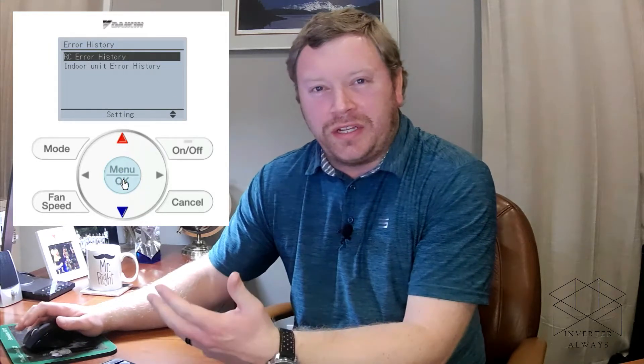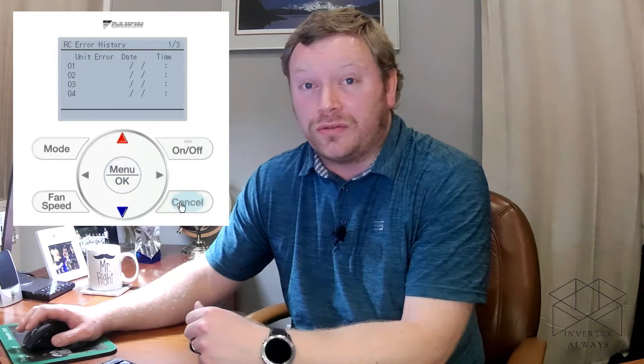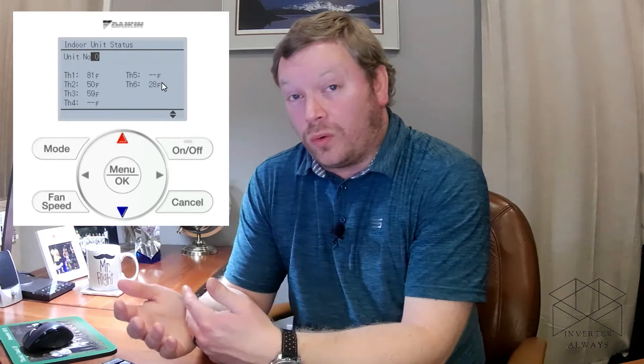You can also extract the error history in the service settings — you're not changing options here, just gathering information. The indoor unit status gives you thermistor data including return air temperature, liquid and gas pipe temperatures, and the remote controller temperature. It also tells you whether the system is using the remote controller or the return air thermistor for temperature control.